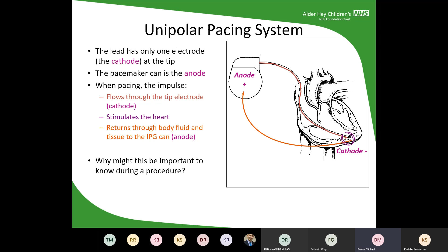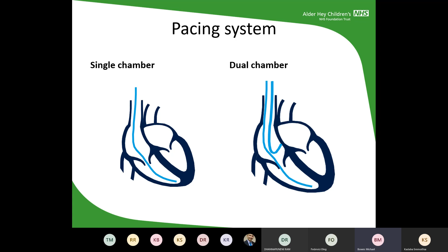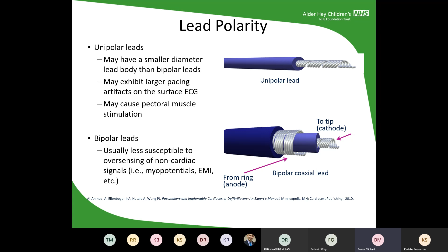Again, a whistle-stop tour of what pacing is. The most simplistic pacing version you can have is a single chamber device, whether that's VVI or AAI. The leads can be unipolar or bipolar. Unipolar leads are smaller diameter and have a big pacing spike on the ECG if you've seen one, but can cause muscle stimulation and are also pretty rubbish at sensing due to myopotentials being picked up, or EMI. Bipolar leads are much better at sensing with fewer issues with that, and usually their thresholds are lower too.